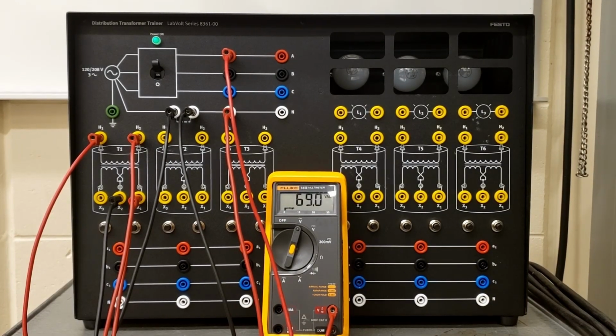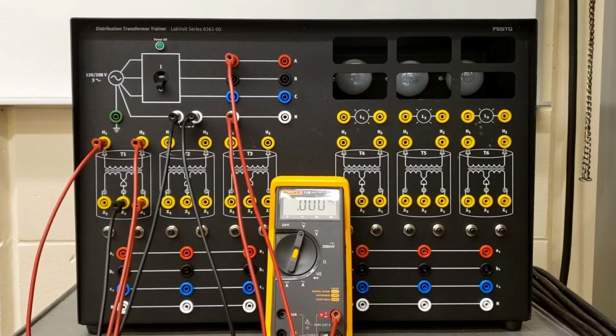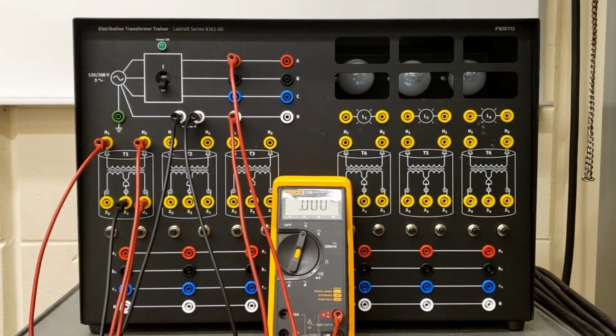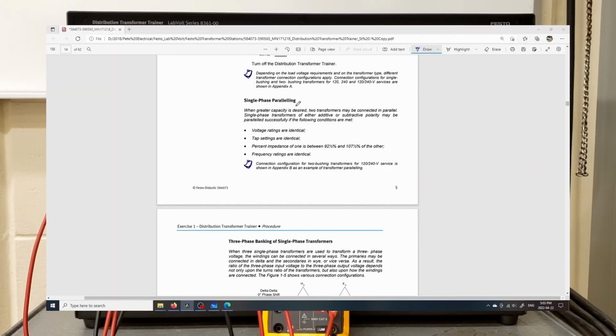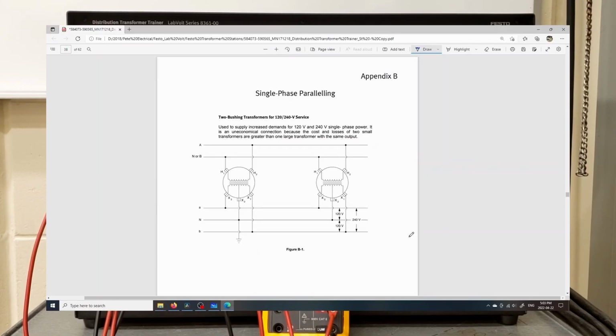Looks good. We'll stop there because the next one is single phase paralleling on page 6. So on page 6 of the instructor manual, let's make sure that's the same page here. So now we're off by 1 page. So at the bottom of page 5, it says single phase paralleling. When greater capacity is desired, two transformers may be connected in parallel. Single phase transformers with either additive or subtractive polarity may be paralleled successfully if the following conditions are met. Voltage, tap ratings, percent impedance, and frequency ratings are basically identical. And it says connection configuration for two bushing transformers for 120 volt 240 service is shown in Appendix B. So in the instructor manual, that is page 33. In the student manual, that is page 29.